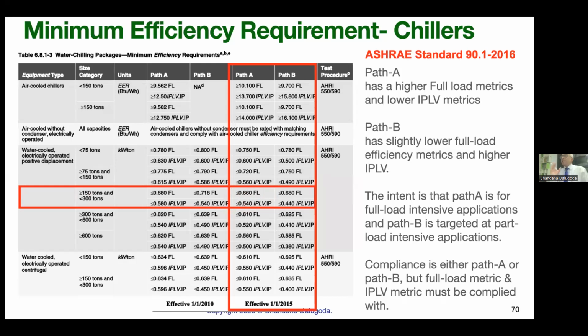Because chillers are not operating at full load all the time. Most of the time, chillers in a building are operating at part load. So we'll have to check. No point in purchasing a chiller if the full load efficiency is great. When the chillers are operating at part load, the efficiency should be higher. That is what is given here.